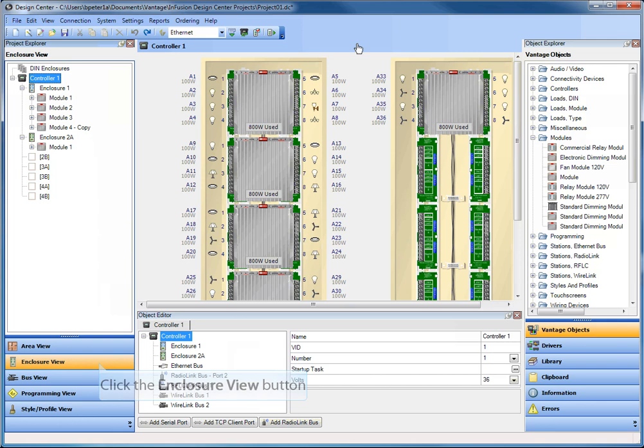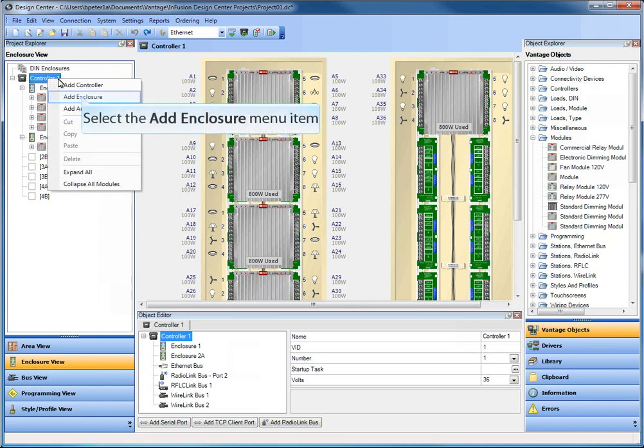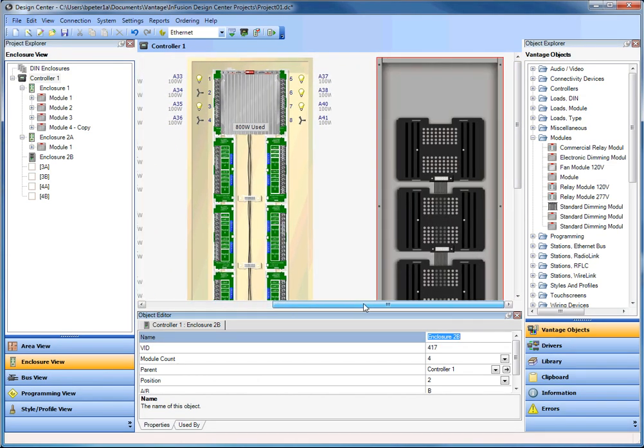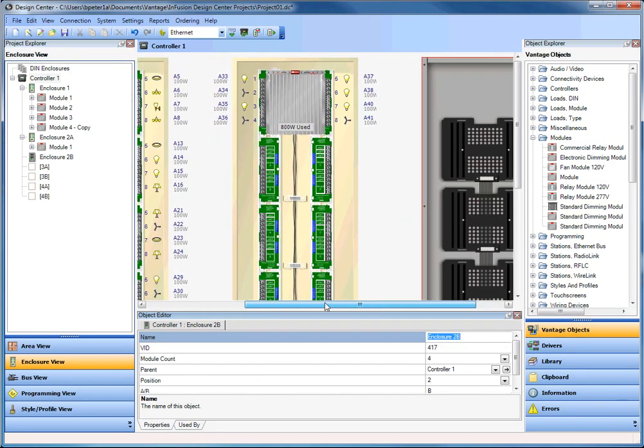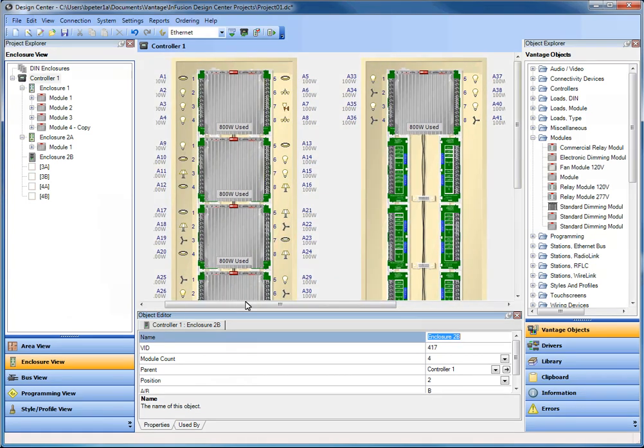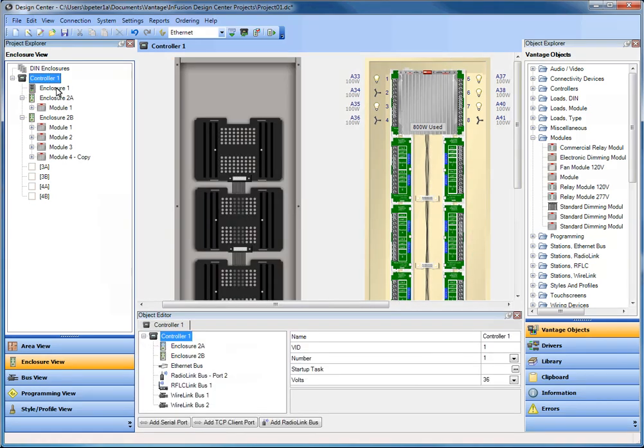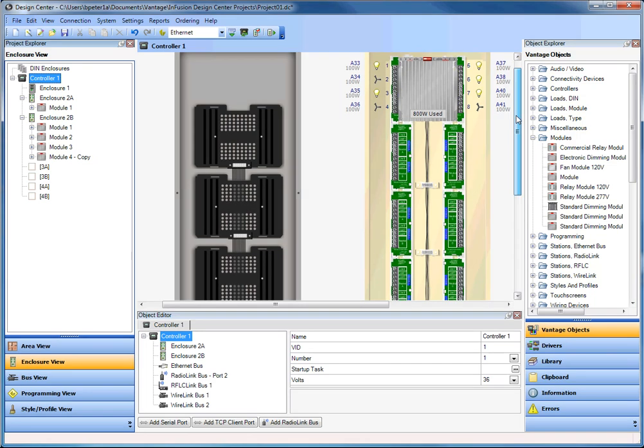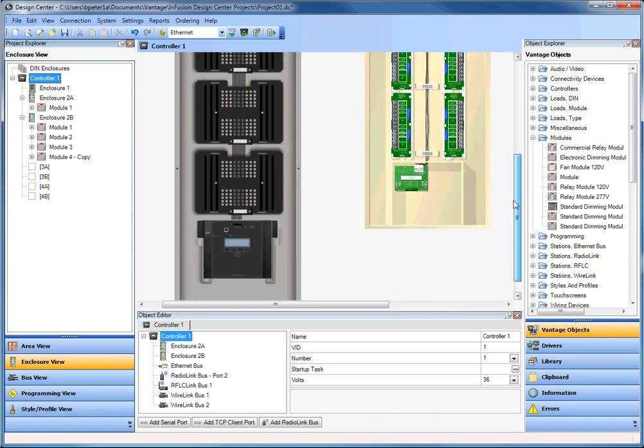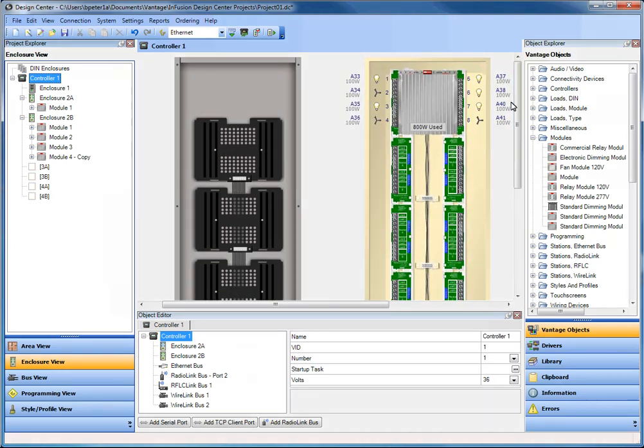So let's look at the first scenario where we want to change out an entire enclosure and module set. So what I would do is here I am in an enclosure view, this is 3.0 update 2, and you can see I've got a couple of legacy or older enclosures in here. I'm going to come up to the tree and right click and I'm going to add an enclosure. So now it's going to add a new enclosure. But what I'm going to do is take the new enclosure that was added and swap it, drag it on top of position number 1. That will force it to be a master or a main enclosure version with a controller. So you can see we've added a controller to that, force it in the right position.